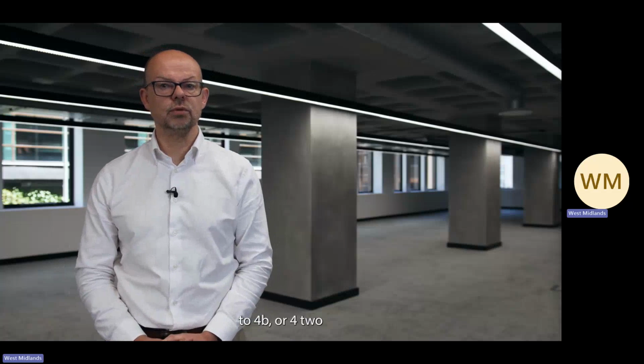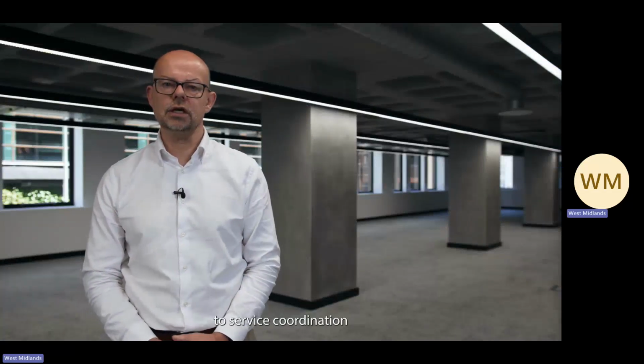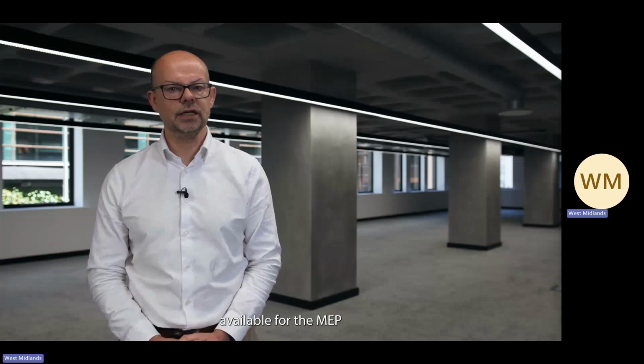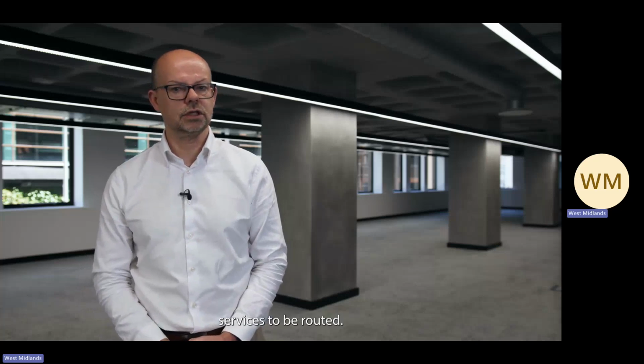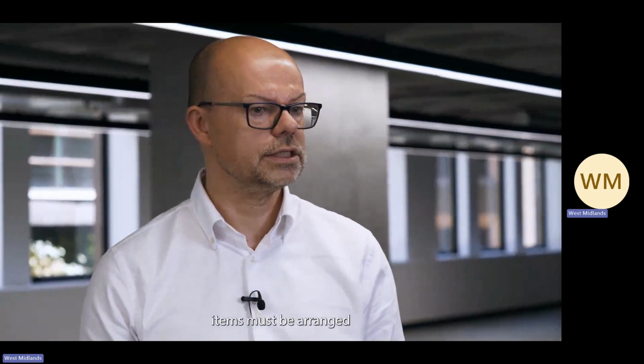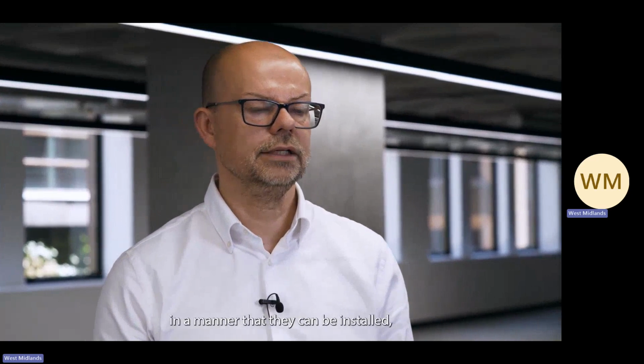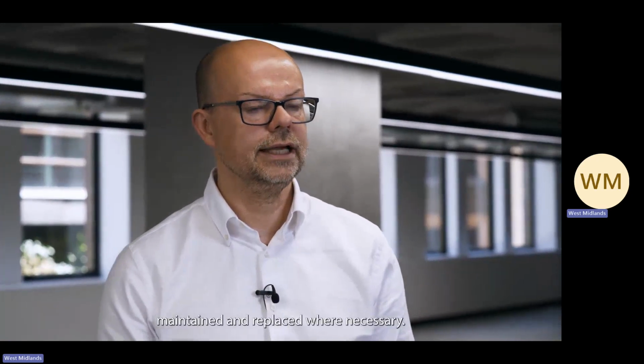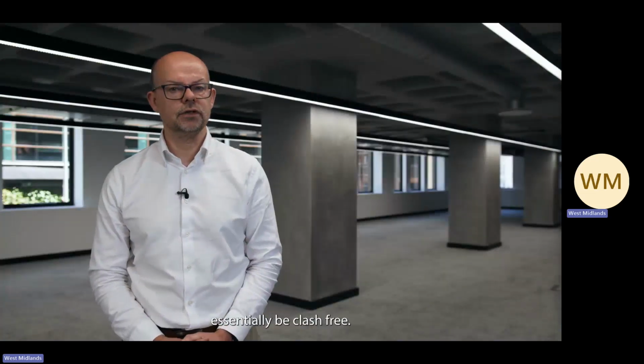Coordinated generic design is the development of the model from stage 4A to 4B or 4.2 and involves the change of the word feasible to coordinated. So the main content of the work at 4B is the service-to-service coordination within the bounded spaces available for the MEP services to be routed. All services, apart from the final pipework connections to equipment items, must be arranged in a manner that they can be installed, maintained and replaced where necessary. The model should essentially be clash-free.